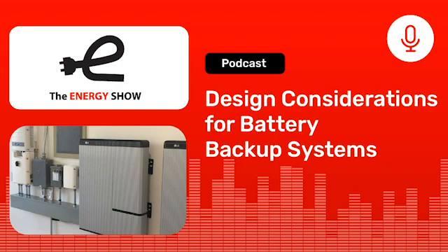There's going to be limitations on the electric service of your house and the system you're putting in. Typically, most systems have a 200 amp electric service, and it may be difficult or impossible to put more than 2 batteries on that service without upgrading it to 400 amps, which could be expensive.